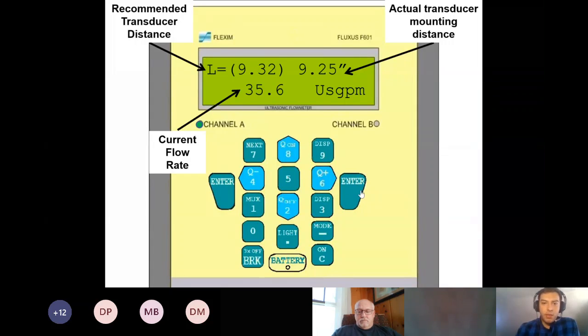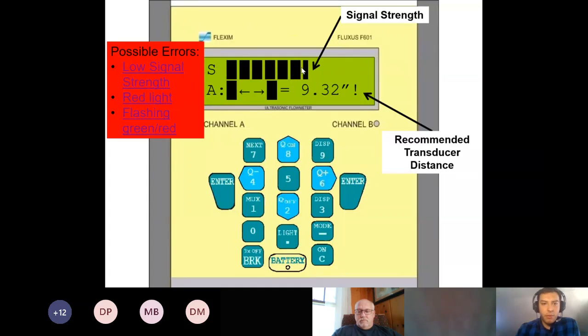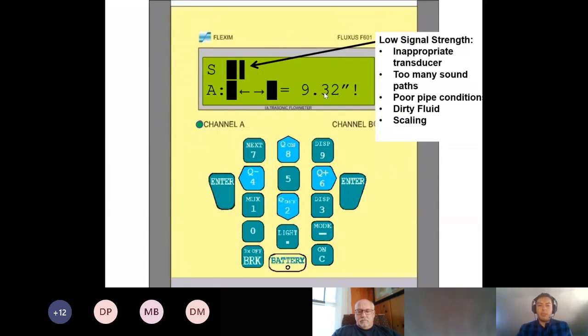Diagnostics for this. I was telling you guys about the signal strength before. If you have less than 3 bars, if you have a low signal strength, there's a few different reasons for this. One could be maybe an inappropriate transducer. If you're using too small of a transducer on too large of a pipe, or maybe the pipe material is ductile iron. A cement-lined ductile iron can be kind of tricky, so sometimes you need to use a larger transducer for that. Going to a larger transducer should increase that. You might have too many sound paths, so if you have maybe 4 sound paths, decrease it to 2. If you're doing a 2 sound path, maybe try the 1 sound path and do a direct mount.